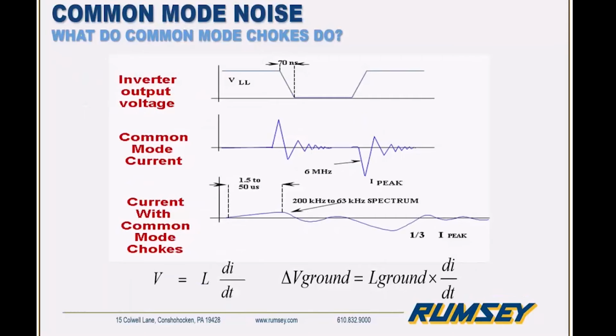Okay, so common mode chokes are effective at reducing common mode current that's created by the drive. Drives use pulse width modulation to control the speed of a motor. That rapid switching of the voltage on the output creates a current form that looks similar to what we see in the middle of this chart. When we add the common mode choke, it effectively dampens the peaks and the ringing from that waveform, as we see at the bottom.